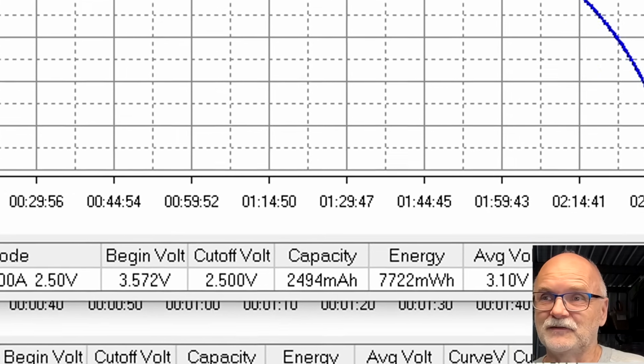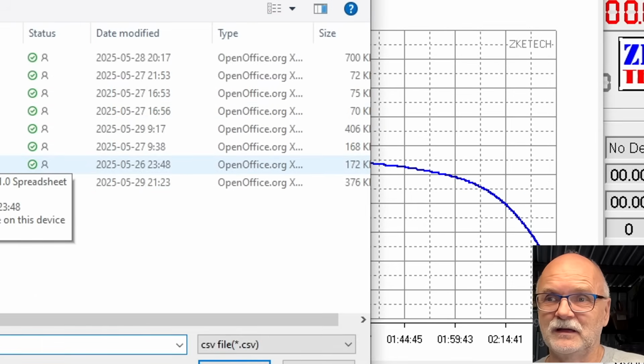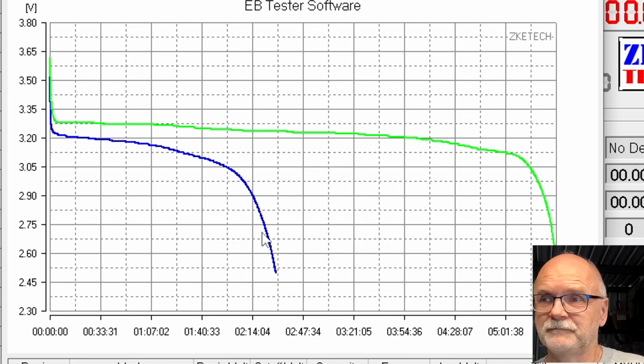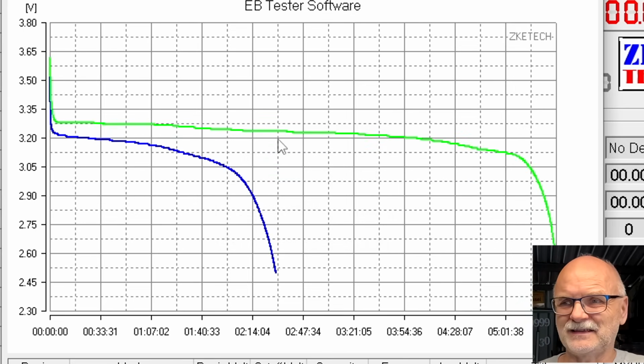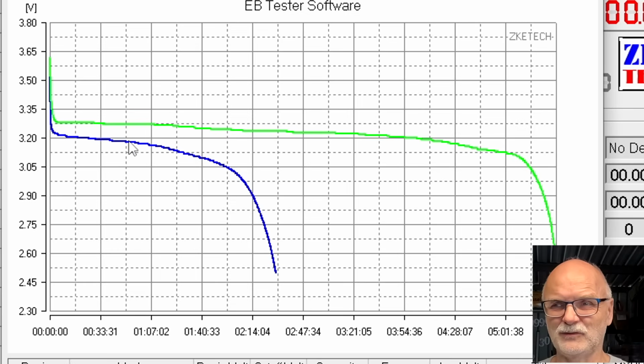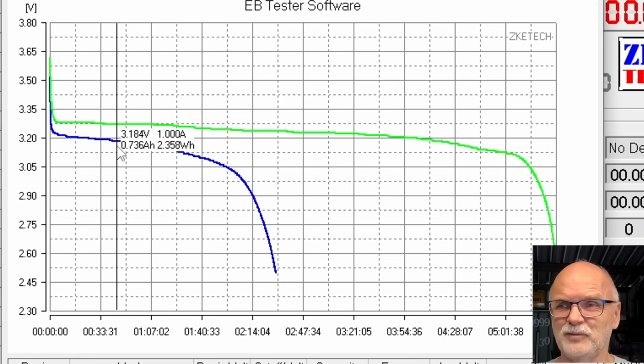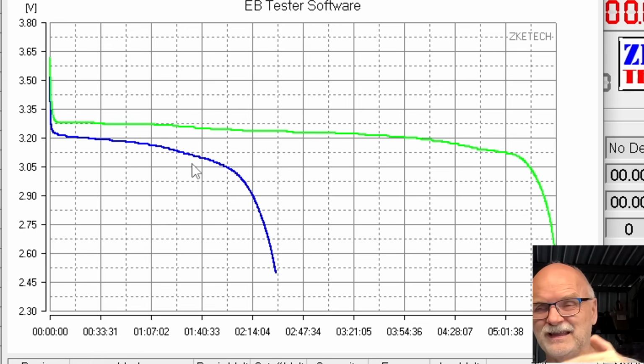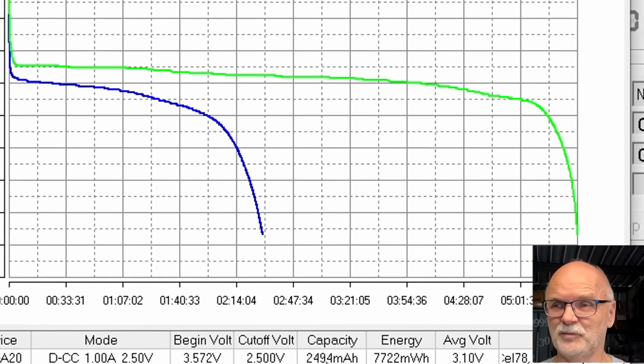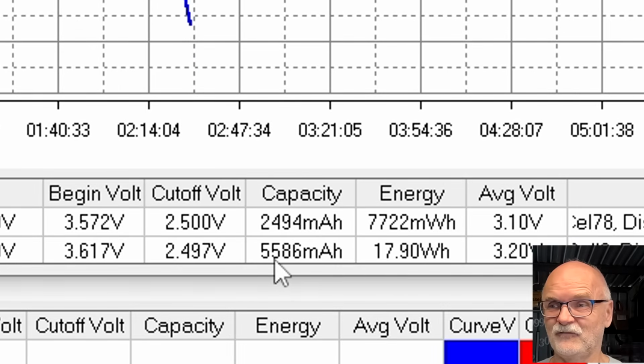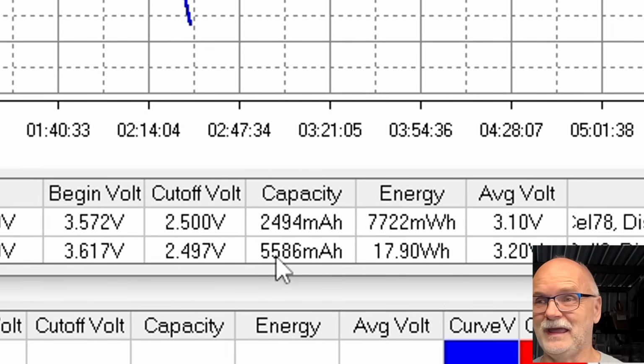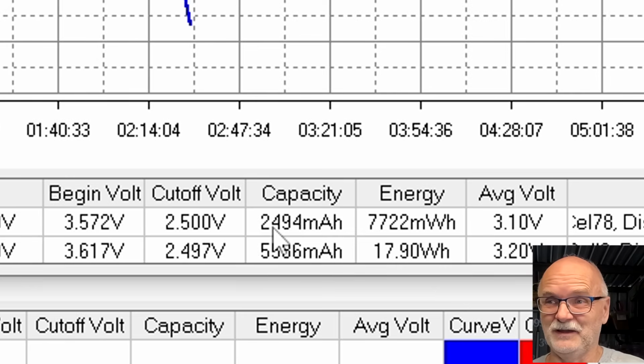So let's open cell number 8's discharge curve in green. It looks like cell number 8 holds the voltage a bit longer and is a bit flatter, while cell 7 goes down relatively early, at around 3.2 volts, and doesn't hold the voltage as well. That's the takeaway: cell number 7 gave 2.5 ampere hours, cell number 7 gave 2.5 ampere hours — less than half the capacity of cell 8.